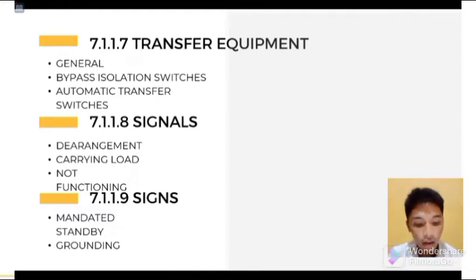7.1.1.8 Signals. Audible and visual signal devices shall be provided, where practicable, for the purposes described at 7.1.1.8 letters A, B, and C. Letter A. Derangement. To indicate derangement of the standby source. B. Carrying load. To indicate that the standby source is carrying load. Letter C. Not functioning. To indicate that the battery charger is not functioning. 9. Signs. A. Mandated standby. A sign shall be placed at the service entrance indicating the type and the location of on-site legally required standby power sources.